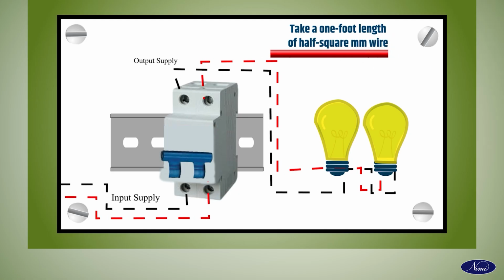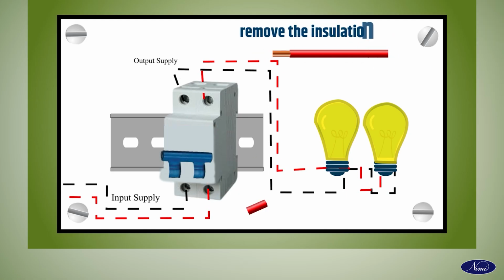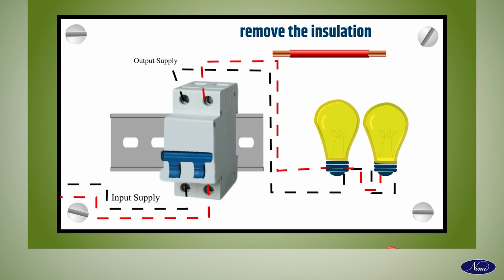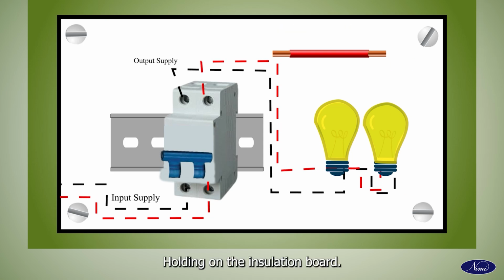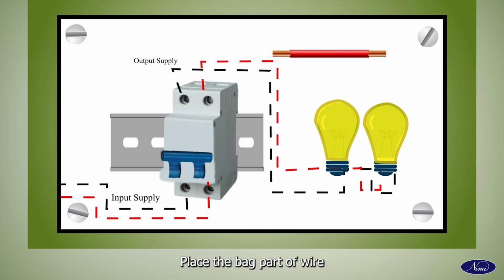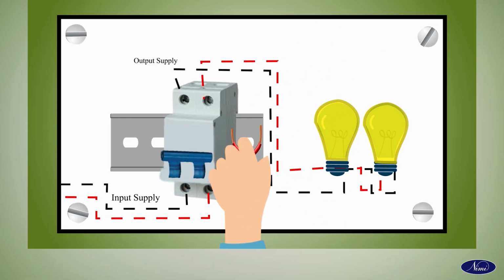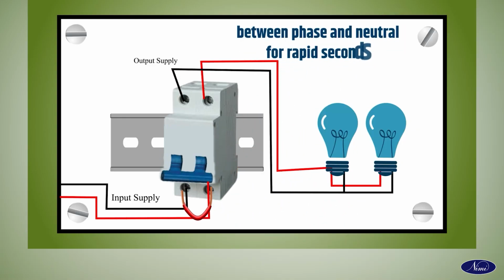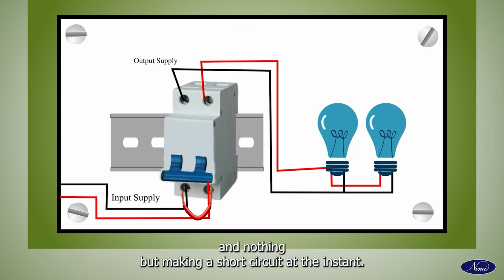Take a 1 foot length of half square millimeter wire. Remove the insulation on both sides of the wire. Holding on the insulation part, place the bared part of wire between phase and neutral for a few seconds, which is nothing but making a short circuit. At that instant, the MCB will trip and disconnect the power supply to the load.